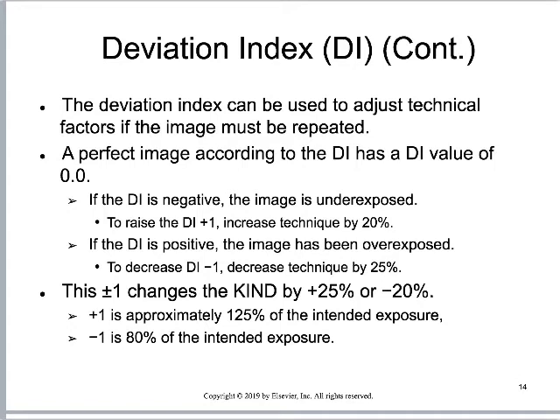How do we use the deviation index? We can use it as a simple measure: do I need to adjust my technical factors? Did I give sufficient exposure? Did I overexpose the patient? The deviation index tells me a simple yes or no. If the DI is negative, the image is underexposed — to raise it by plus one, increase technique by about 20%, increase the mAs. If the DI is positive, the image has been overexposed — decrease the mAs by about 25%. Each plus or minus one in the deviation index indicates an indicated air KERMA difference of about 25% to 20%.